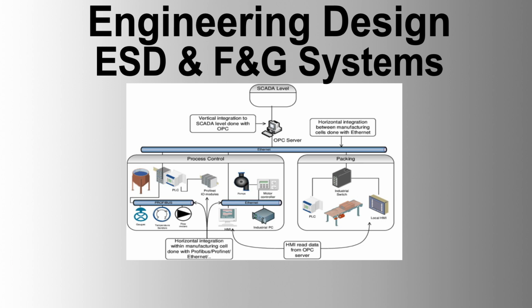Documentation required on delivery. 1. As-tested documentation. All drawings and documentation must be updated to reflect the as-tested status, incorporating any modifications and corrections identified during FAT. 2. Final documentation package. A complete set of updated documents, including system schematics, configuration details, test reports, and certificates. Documentation must be organized and indexed for easy reference and retrieval. By adhering to these documentation requirements, the ESD F&G system will be thoroughly supported with clear and comprehensive information, facilitating proper installation, operation, maintenance, and management.